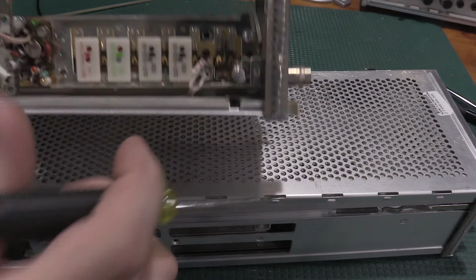You can see more of these micro switches. Because I've had my hands all in here, I'm going to pop these out. I'll adjust the spring tension on the micro switches as well, or on the switches up here. And then I'll hose this all down with isopropyl. I got that aerosolized can of ISO. We'll hose this down, run it through the ranges, just make sure we get some signal through it, and then we'll try to calibrate it and see what happens. The calibration will tell us if we have other issues we need to address.